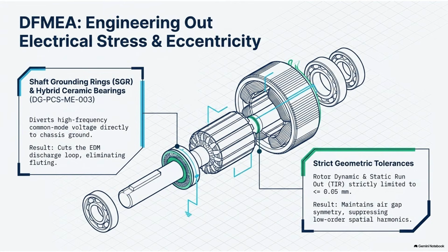So now, when that high-frequency common mode voltage builds up on the shaft, it hits the carbon brush. And the brush is wired directly to the chassis ground. It gives the voltage an easy, entirely harmless path to dissipate. It completely bypasses the bearing. Exactly. You cut off the discharge loop at the source. If the voltage goes through the carbon brush, there is zero pressure on the oil film. No sparks inside the bearing, no micro craters on the raceway, no washboard fluting. The root cause of the wobble is eradicated. And the sources also mention a secondary option if they don't want to use a carbon brush, right? Hybrid ceramic bearings.